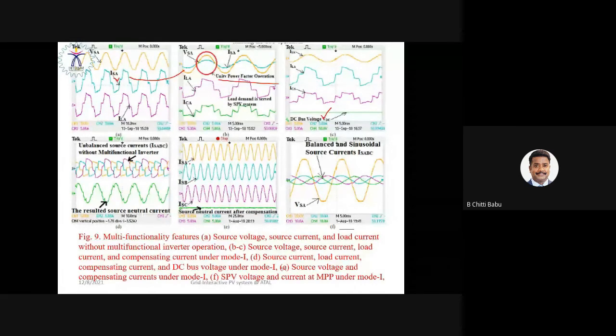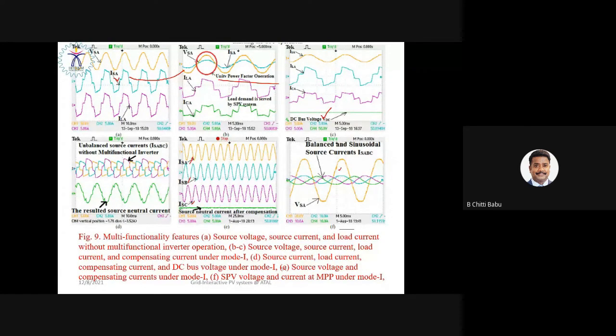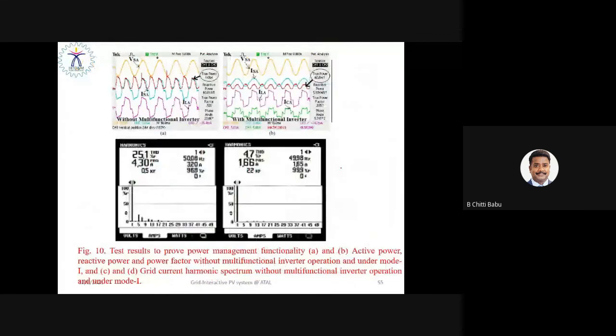This is the response of phase A, phase B, and phase C. Overall, the grid currents are sinusoidal and in phase with the supply voltages. So the grid is free from reactive power burden. And you can see here, without the multifunctional inverter and with the multifunctional inverter, the source current becomes sinusoidal and in phase with voltage. So now, as the lower order harmonics are eliminated by the proposed control strategy, the grid current THD has been reduced to 4.7% from 25.1%. Okay, this is the beauty of the proposed control strategy.